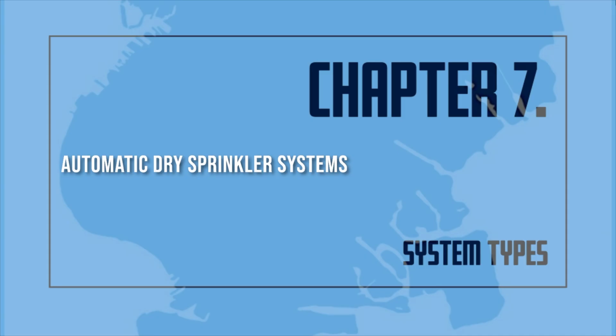Automatic dry sprinkler systems. Dry pipe sprinkler systems are installed where a wet pipe system cannot be heated to prevent freezing. Under normal conditions, there is no water in the piping. Instead, the piping in the system is filled with air or nitrogen under pressure. The air pressure in the piping is controlled automatically by an air maintenance device. The system uses standard sprinkler heads. When a sprinkler head is opened by the heat from a fire, the air pressure is reduced in the piping. The drop in air pressure causes a special dry pipe valve to open. A supervisory device signals when the valve is opened. Then water flows into the piping and out of the opened sprinklers.